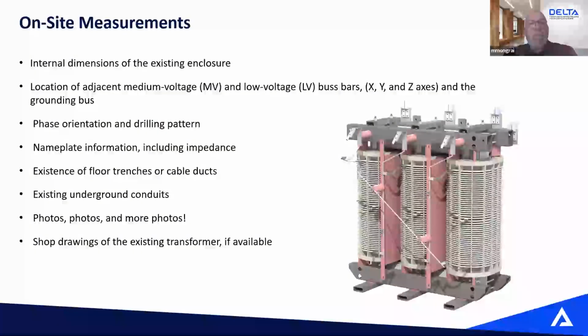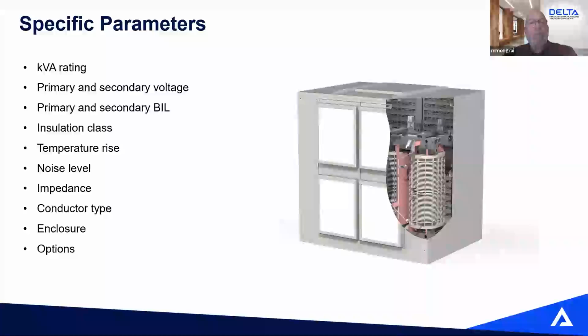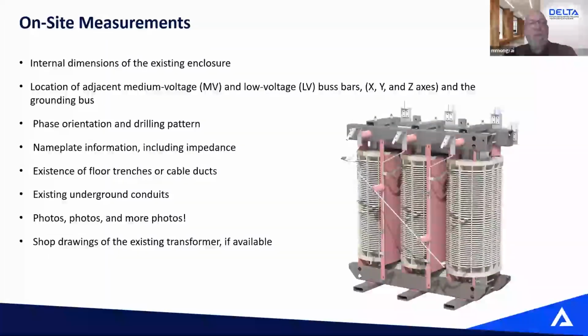So when we replace a transformer, we need to make lots of measures on site. What is important is that we have something that will fit in place, that will connect to the existing equipment if we keep the existing equipment. The main dimension we need is the volume of the inside of the enclosure. We need to know exactly where all bus bars, HV and LV, come in the enclosure from the HV equipment and the low voltage equipment.